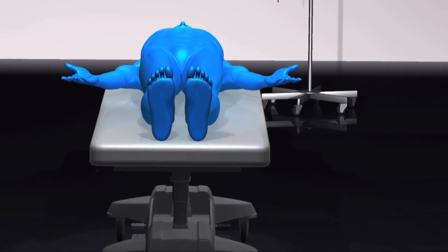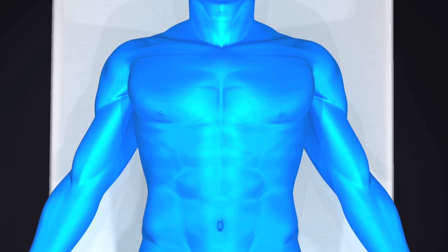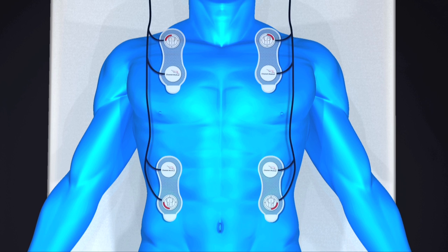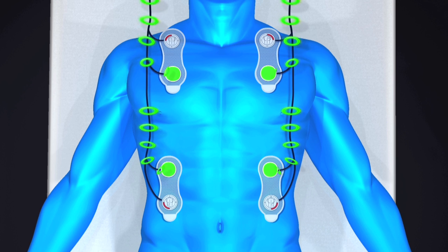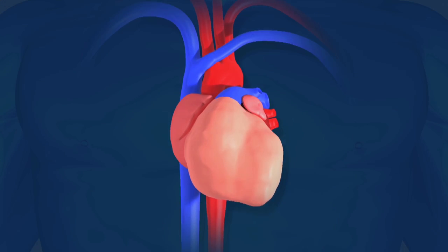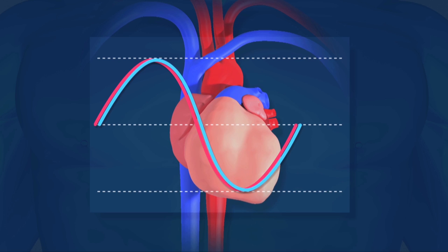It utilizes bioreactance, a technology developed by Cheetah Medical scientists over years of research and development, followed by extensive testing and validation. The basis behind the Cheetah NICOM is the use of time delay or phase shifts, which occur when an alternating electrical current is passed through the thorax. The Cheetah NICOM has eight sensors on four sensor pads. Four outer sensors emit a low-level electrical current, and four inner sensors detect the information and send it back to the monitor. As the heart expands and contracts, a time delay or phase shift is created in the current by blood flow. The monitor then uses this phase shift as a baseline for measurement.